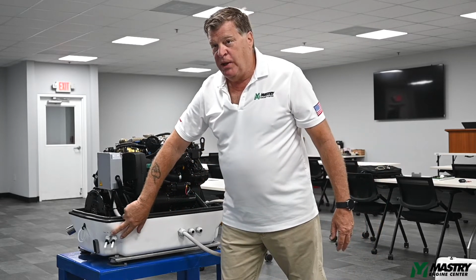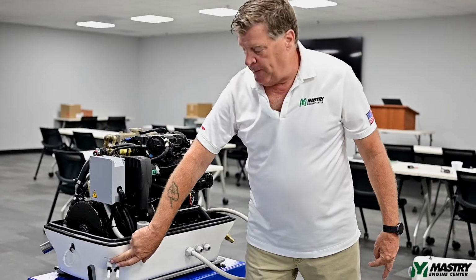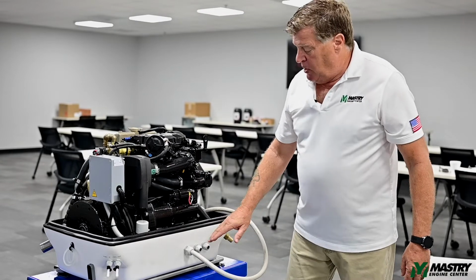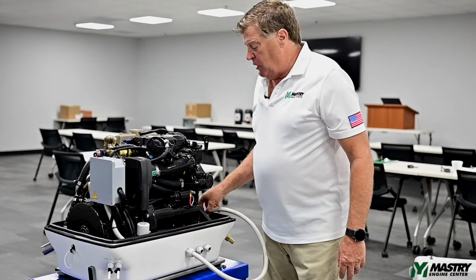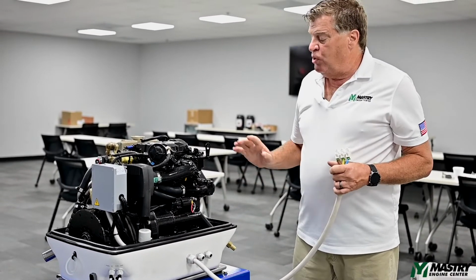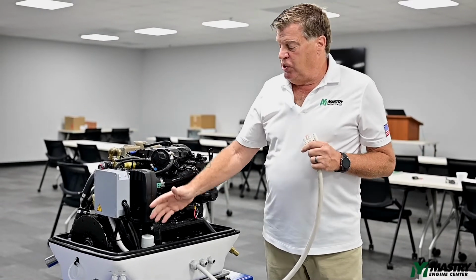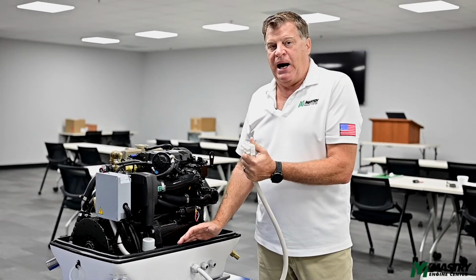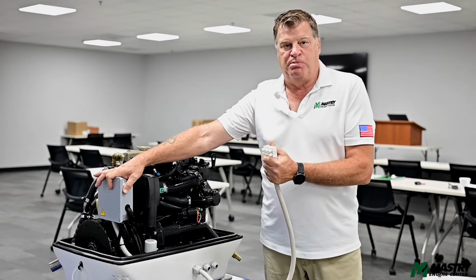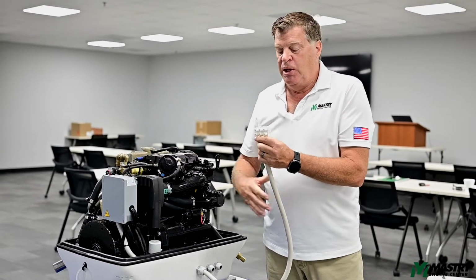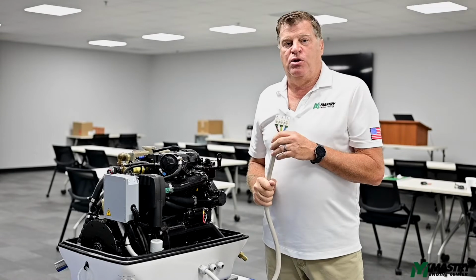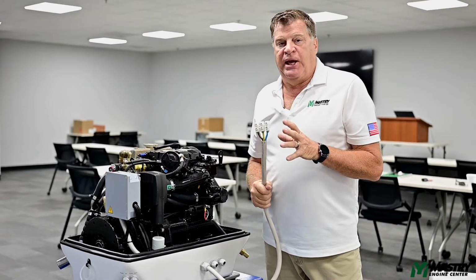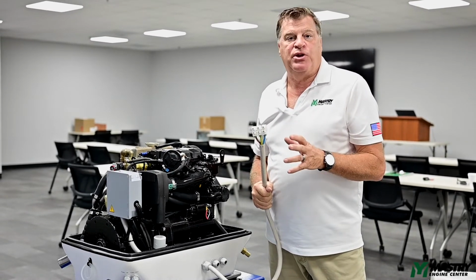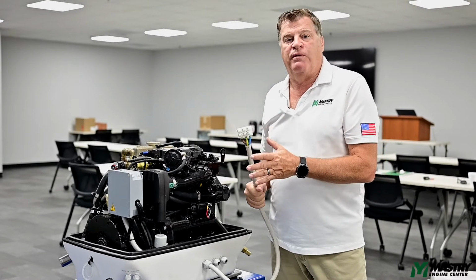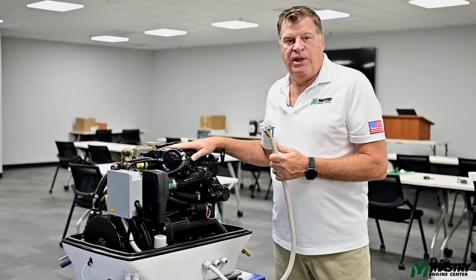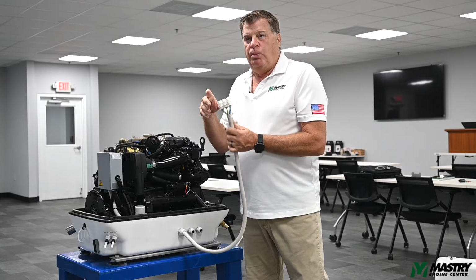These are your 2 feed lines, fuel in, fuel out. They go through bulkhead fittings. This line here is your AC current line. We pre-wire every unit so that your AC current is pre-wired to the outside of the box. You do not need to open up this box at all when you purchase one of these units. This would get wired direct to a box which is going to contain the breaker based on the current that you need, whether it be a 60 amp, 50 amp, 45 amp, whatever the maximum output of the engine is, the breaker box will be connected to this.